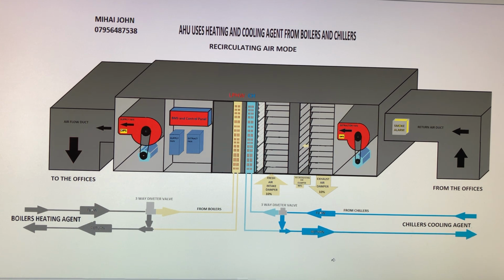Just imagine, I want to tell you something very important. Sometimes there are many air handling units on the roof that use one chiller, and because of that, the chiller might be functional before the BMS calls it to run. It's already running because it has to provide cooling agent to another air handling unit. So anyway, let's assume that the chiller was already running. Then the building management control, as you'll see here, we have a three-way diverter valve, will divert the cooling agent so it goes through this heat exchanger, and it will control this bypass to provide enough energy into this heat exchanger to cool the air.